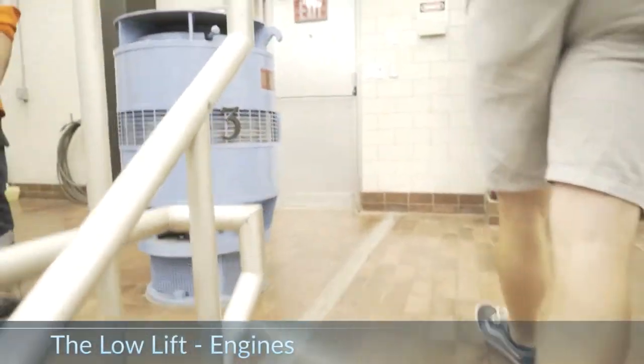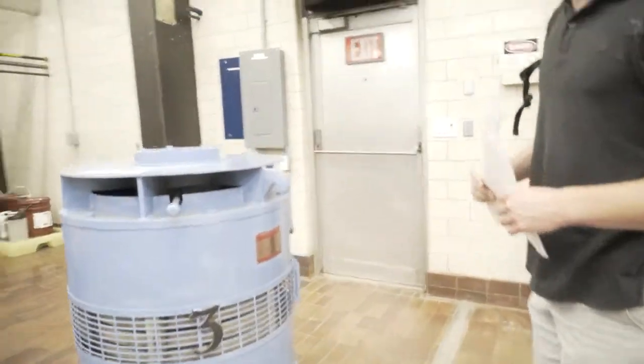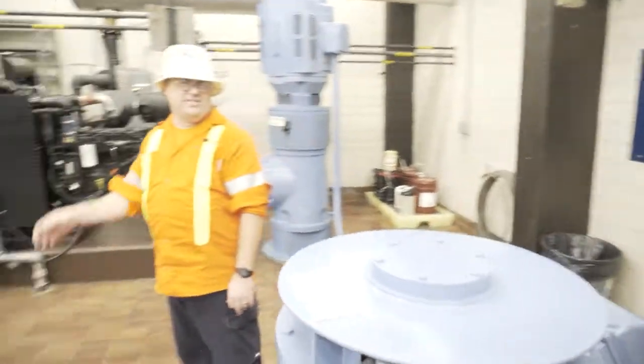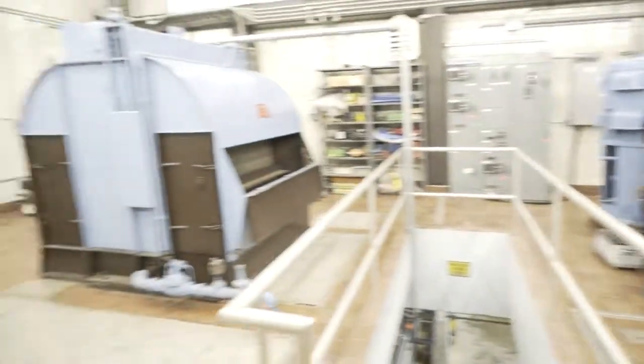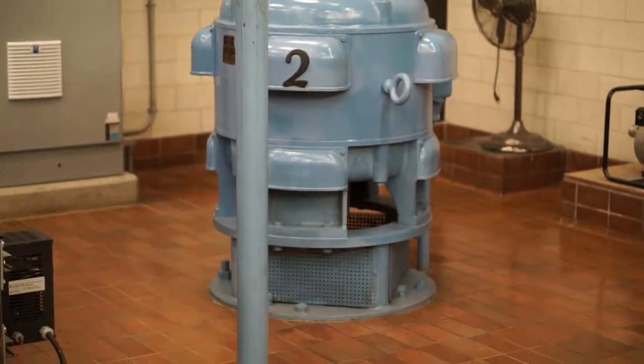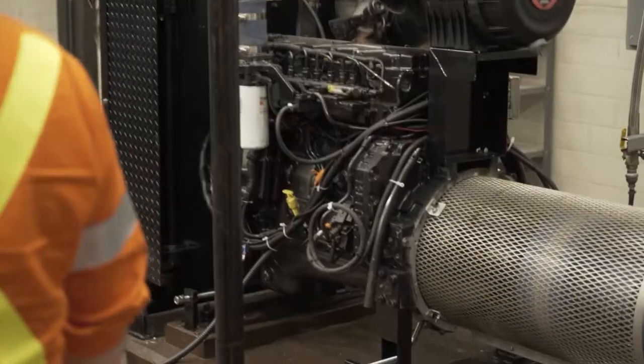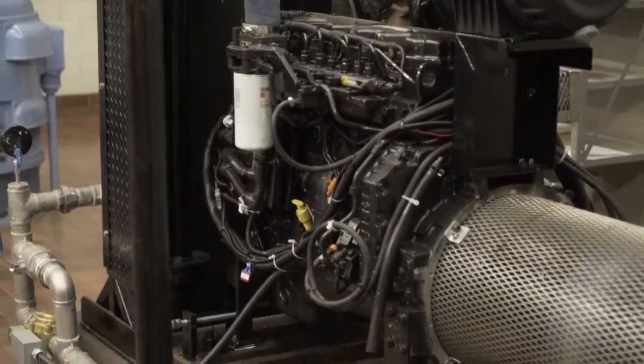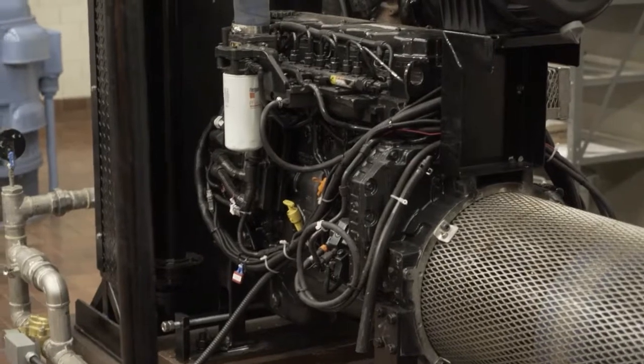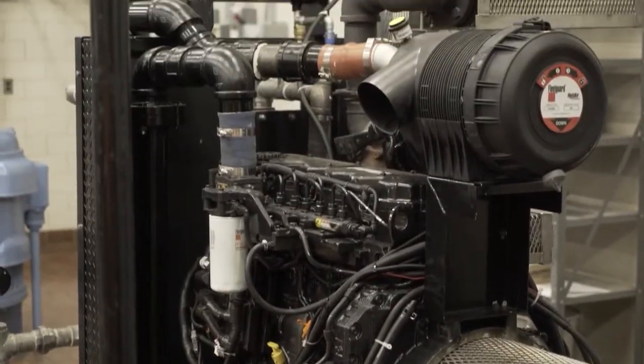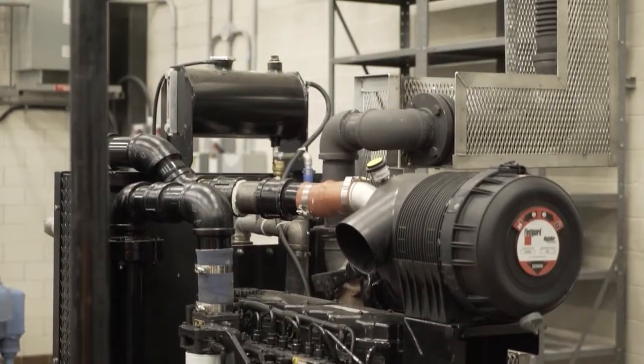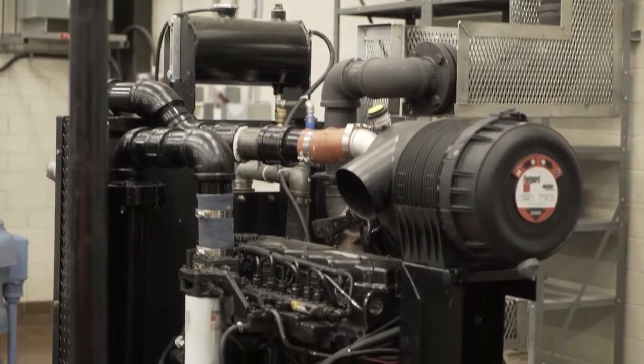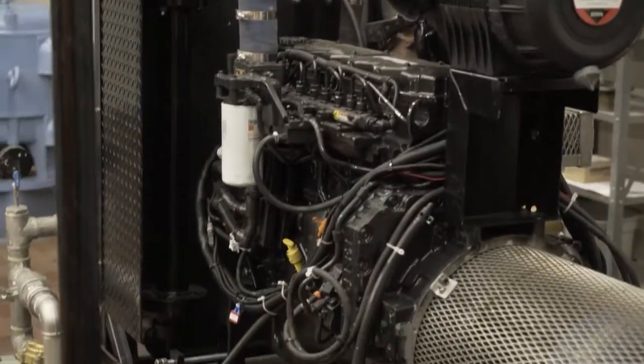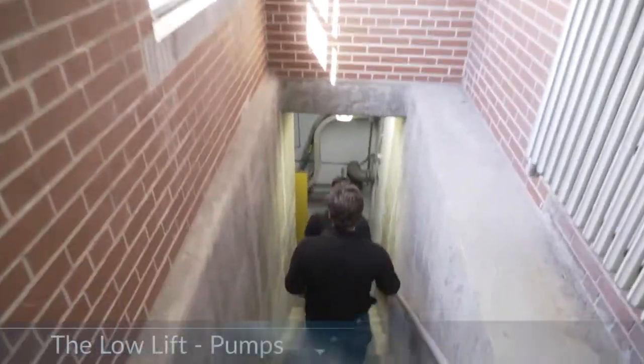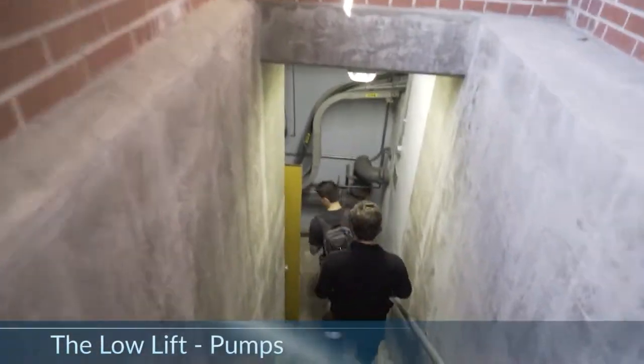The water drawn from Lake Ontario enters a surge chamber, and from there it is drawn into the low-lift building. There are 4 low-lift pumps, 2 electric and 2 diesel, so that during a power outage the diesel pumps still run. This facility contains high-lift and low-lift centrifugal pumps. The low-lift pumps are a high volume with a low pressure rise, and high-lift pumps are the same high volume but with a high pressure rise to reach the municipal supply pressure.